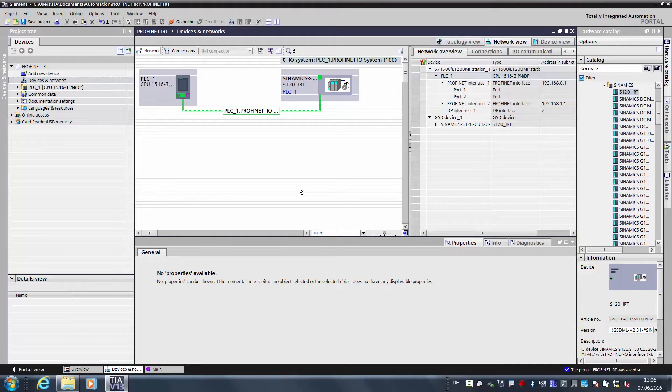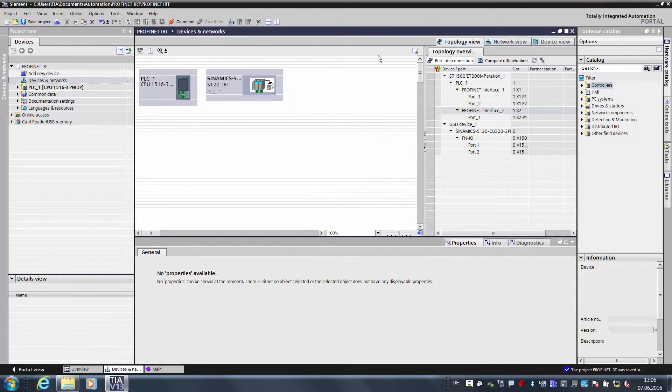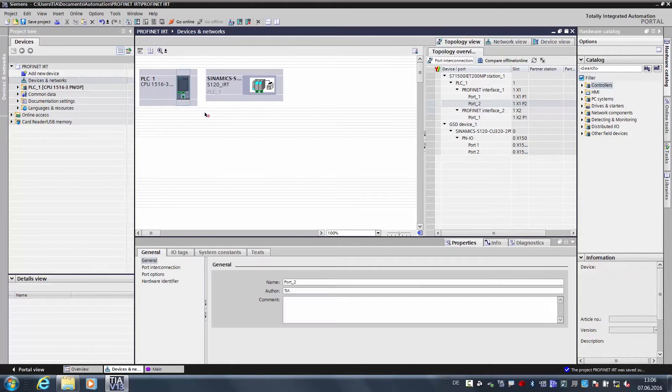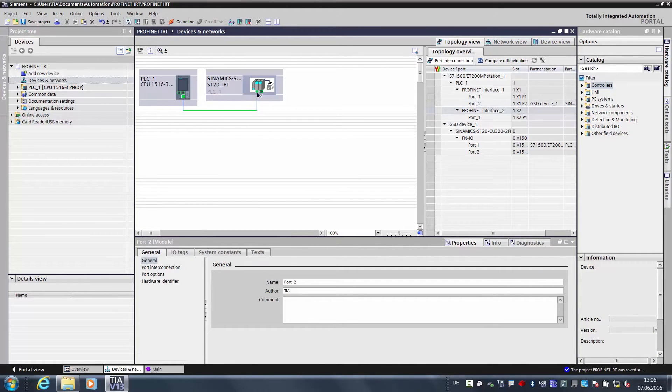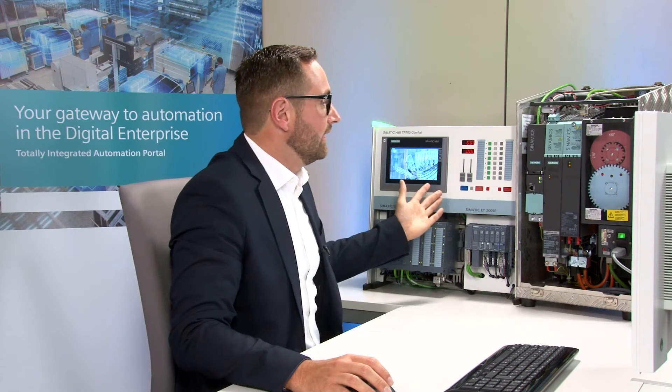And now comes determinism. Determinism means that the timing of the entire system can be precisely determined. To do so, we need to create the topology in PROFINET IRT. In the topology, we will use drag and drop to connect the individual ports to each other, as found in the hardware configuration, and an exact schedule for the message frames can be created as a result. An additional advantage of the topology is that the new device is automatically configured when components are replaced.